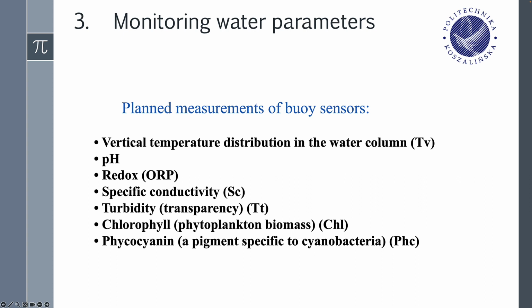Specific conductivity, SC, electrical conductivity measurement is a widely used analytical parameter. It is characterized by high reliability, sensitivity, and short response time, a valuable and easy-to-use tool in water quality control as a non-specific summary parameter for all dissolved ionic compounds, salts, acids, bases, and some organic substances, in the solution. This technique does not allow for distinguishing individual types of ions. The reading is directly proportional to the combined effect of all ions present in the sample.